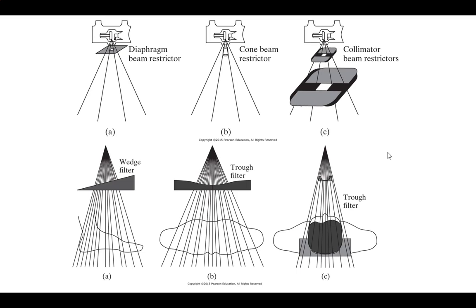Okay? And so placing that inside as a filter, you get your X-ray radiation coming out, it's been collimated, and I can go through a wedge filter. Sometimes they'll have another collimator, just to prevent any spreading that's going on. And I can use that, and now I've got the proper range of frequencies going through, so I can get a very good contrast and see all the structures.